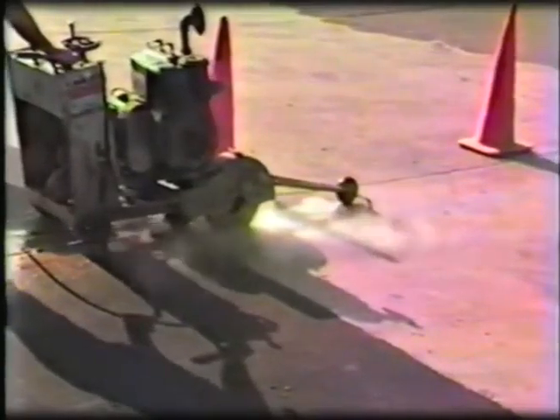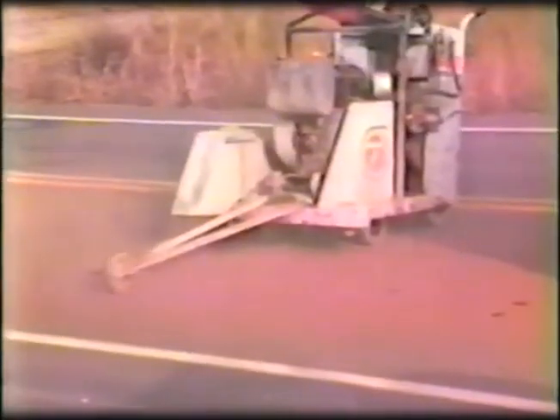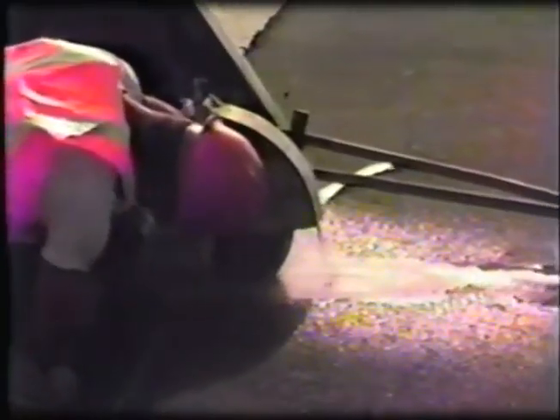Masonry saws for loop installations are available in a range of sizes and sawing capabilities. This is an 18-horsepower saw with a diamond blade in a wet-cutting operation. This was found to be a most efficient method. An 18-horsepower saw is preferable to the widely used 9.5-horsepower model. The smaller model is slower and breaks down frequently due to excessive workload. A variety of saw blades can also be used in loop installation, but the diamond blade is considerably faster, neater, and perhaps safer than traditional dry-cutting abrasive blades.